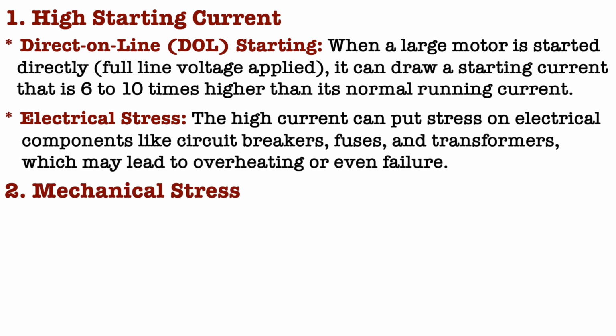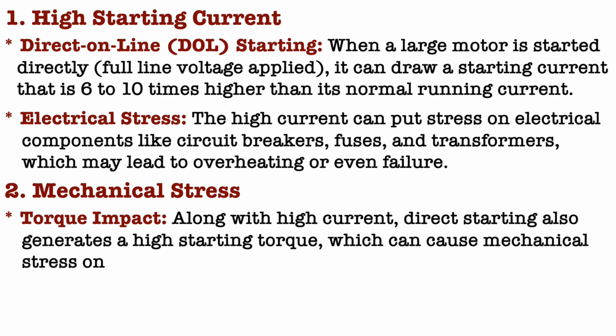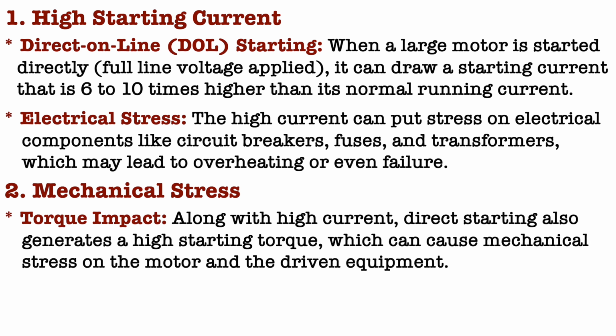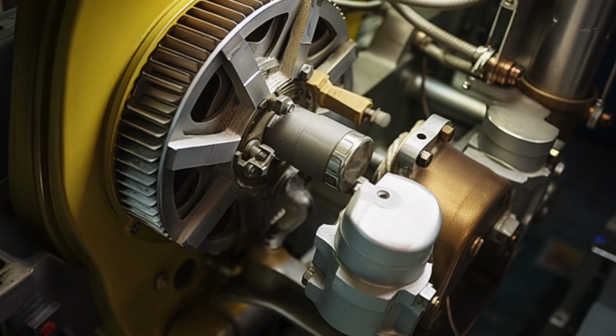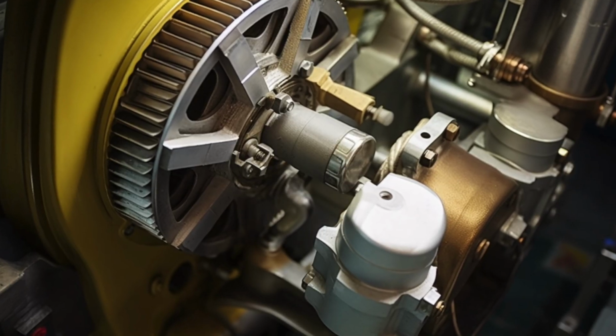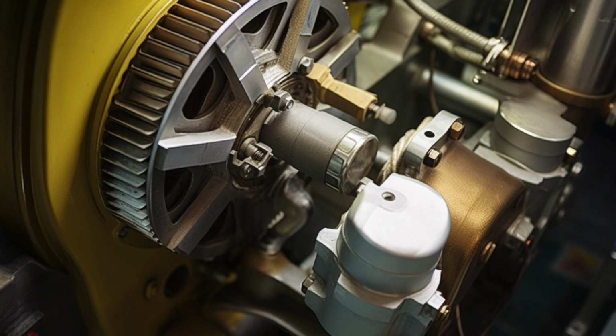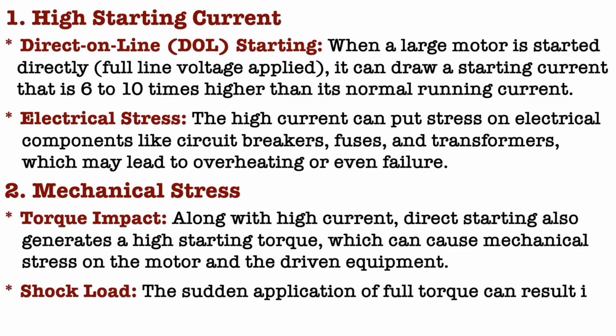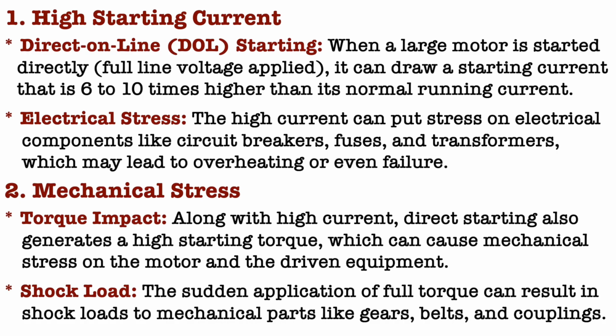Under this, first one is torque impact. Along with high current, direct starting also generates a high starting torque, which can cause mechanical stress on the motor and the driven equipment. This can lead to excessive wear and tear, reducing the lifespan of machinery. Next is shock load. The sudden application of full torque can result in a shock load to mechanical parts like gears, belts, and couplings.